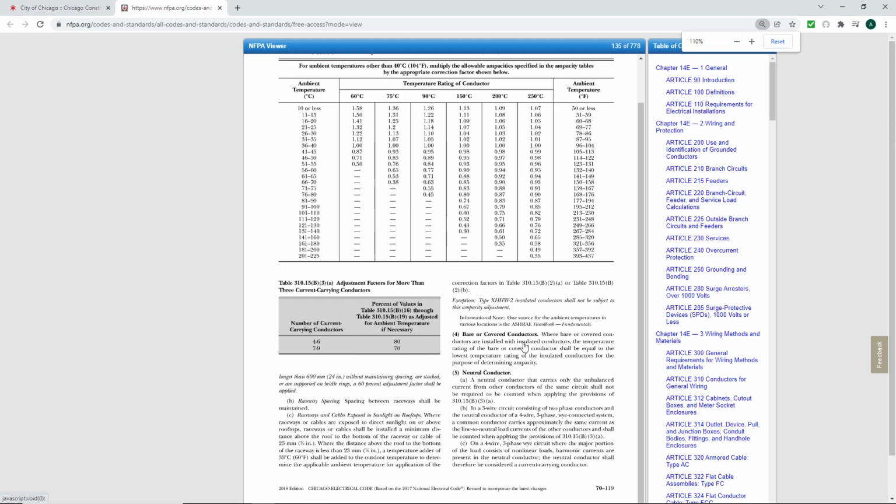Now, I don't know if that's the reason why they like to use XHHW, because the insulated conductor probably won't mess with the ampacity that conductor can withstand. Because it's underground, the heat that's produced can't really go anywhere, so that pipe would start to heat up on the inside, and you start to drop your ampacity. I don't believe with that insulated cable itself, the adjustment would apply.